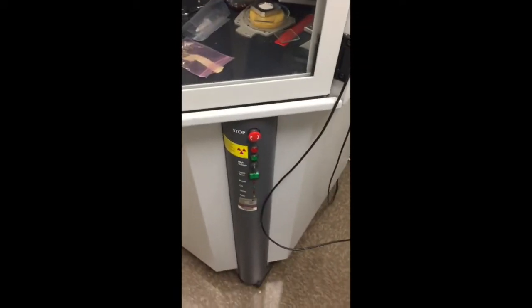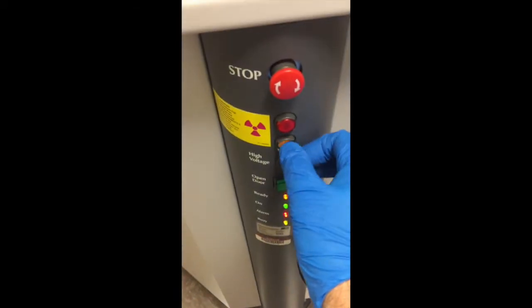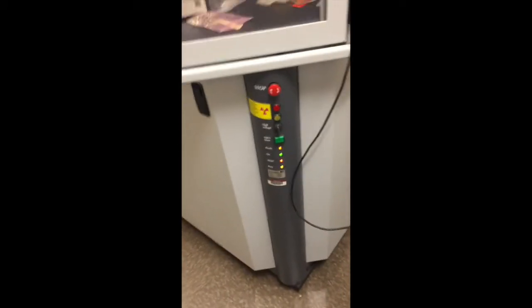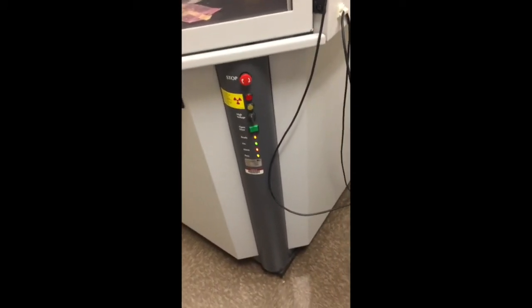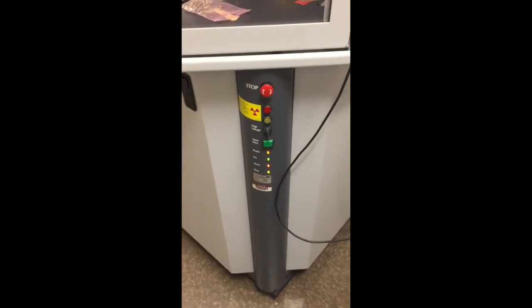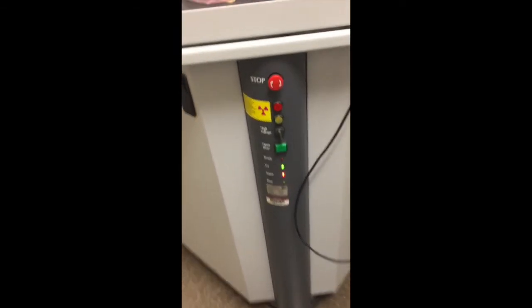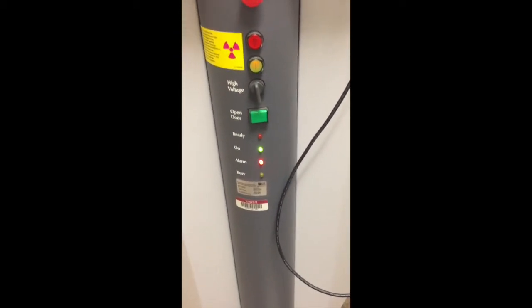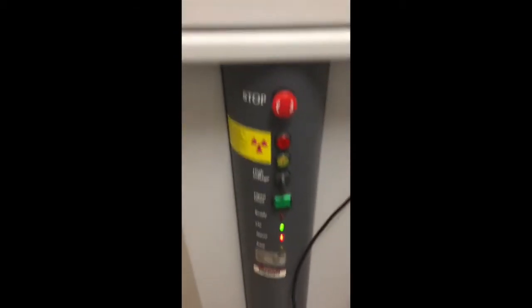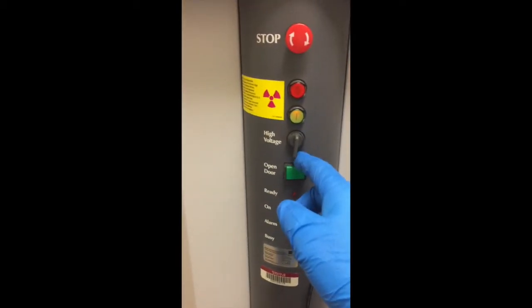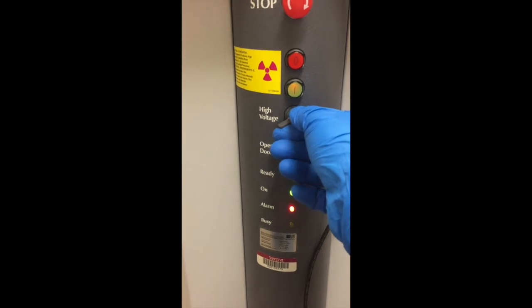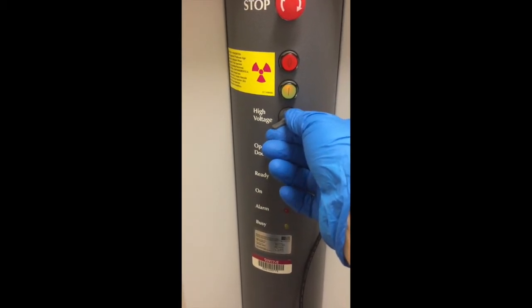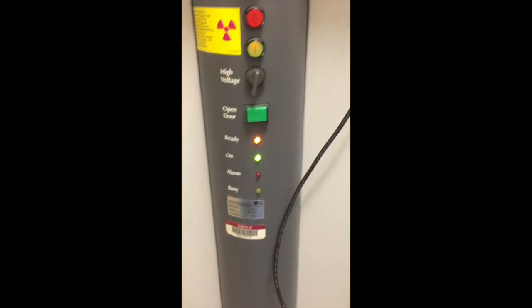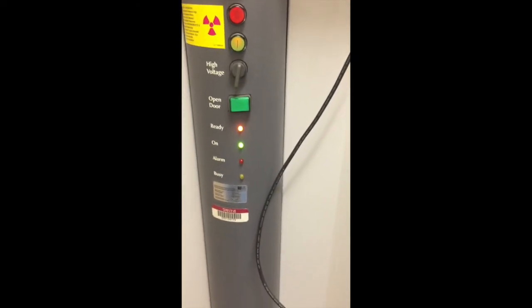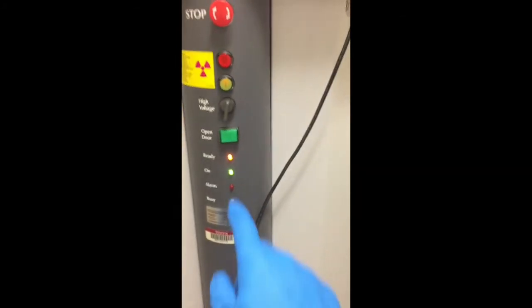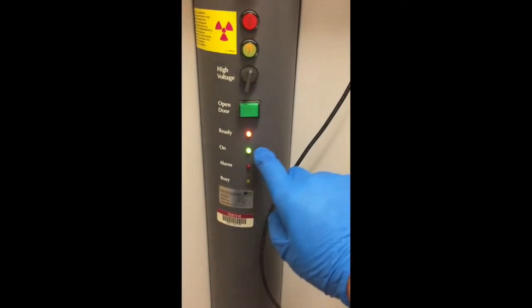After the chiller's on, we press this green button and then wait for those 4 lights, 2 on the top and 2 on the bottom, to go away. Okay, now 2 lamps are on. And then next thing is to use this knob that says high voltage and hold it about 45 degrees clockwise. And you hear 2 clicks and then let it go. You don't have to do it real hard or anything. Okay, now the 2 lamps are on, it's ready and on.